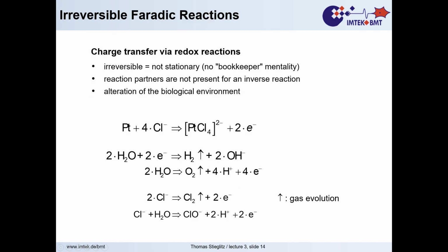If we go into corrosion, something we don't want to have, but we should know about that. It's irreversible, that means not stationary. You can reverse the polarity of the pulse, but it doesn't help because the kinetics of the reactions is different in one direction and the other. That means you have to prevent overdoing your electrical stimulation and always stay within the limits that do not cause that irreversible Faradic reaction.